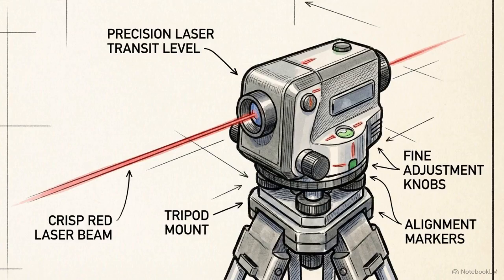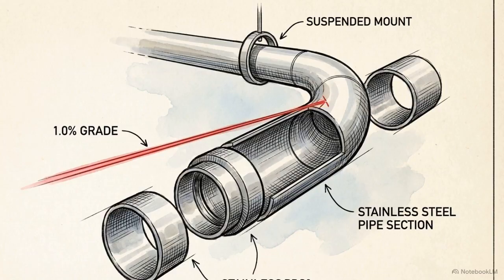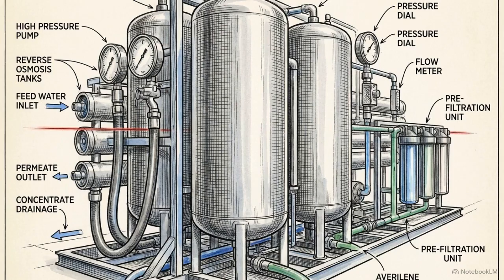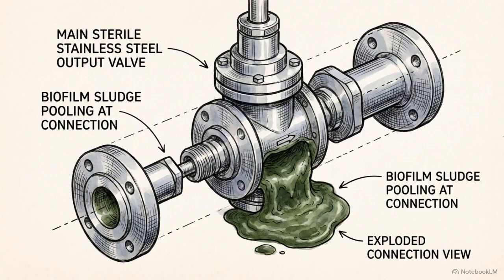We use a high-precision laser transit level to verify this pitch across the entire length of the run, ensuring that no section of the pipe is perfectly horizontal. Without this verified baseline pitch, the effectiveness of the purification technology, from reverse osmosis to distillation, is compromised by localized stagnation.